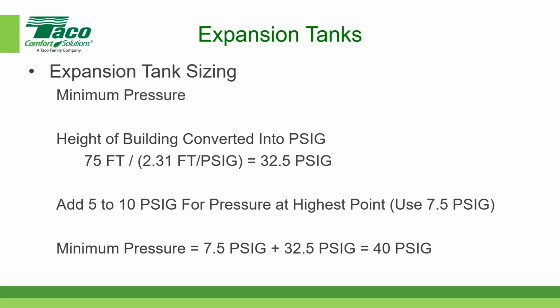When you were a consulting engineer, did you include that value on your schedules or somewhere in your documents? Yes, we always have to include the minimum fill pressure that we need at the expansion tank. Now remember, in our case for tonight's discussion, the expansion tank is at the bottom of the building. If the expansion tank is at the top of the building, the calculation is slightly different. If we have a little time later after we get through some of these questions, we can show what the effect is of putting the expansion tank at the top of the building. And then, any other questions out there? Well, we might be able to answer this one and then you can continue on.